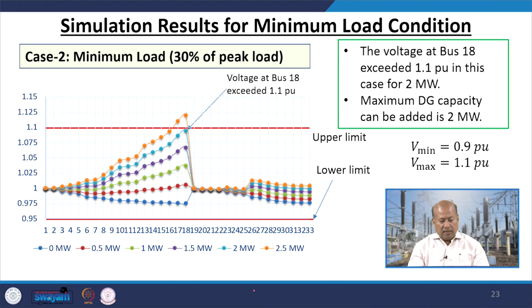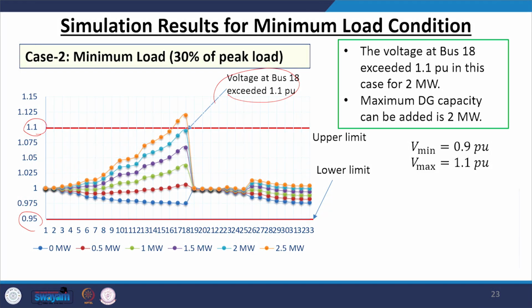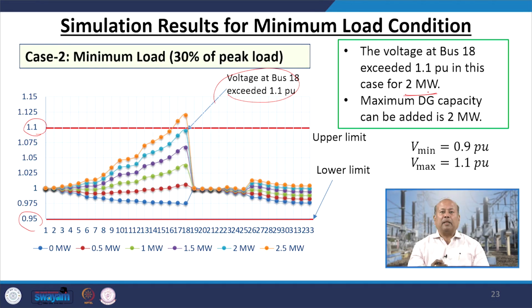So, where the lower limit is given as 0.95, the maximum is going to be 1.1, and the voltage at bus 18 exceeds 1.1 per unit when it is crossing 2 megawatt. Very interesting. So, what does it mean? The voltage at bus 18 exceeds 1.1 per unit in the case of 2 megawatt of penetration. So, the maximum DG capacity that can be added is 2 megawatt, all right.